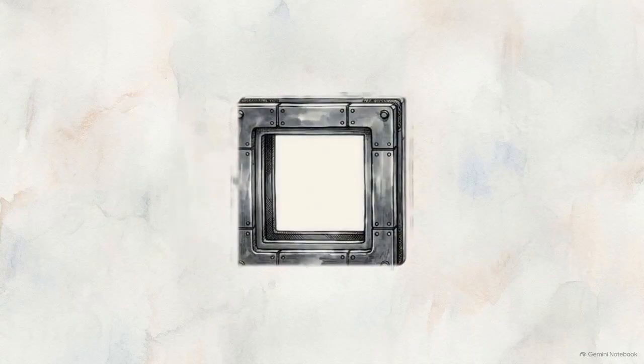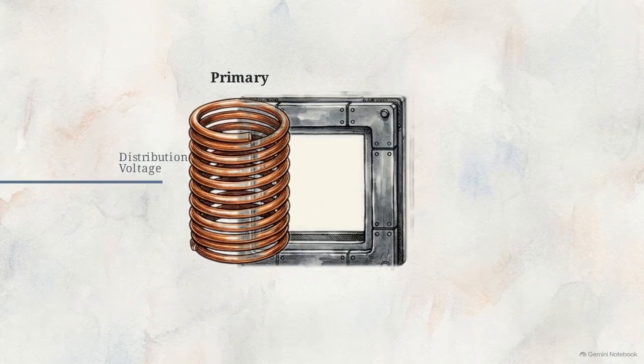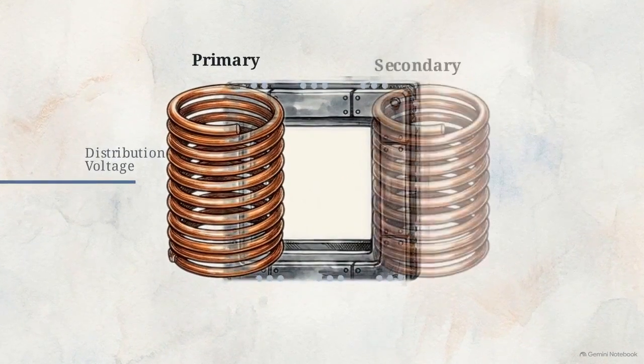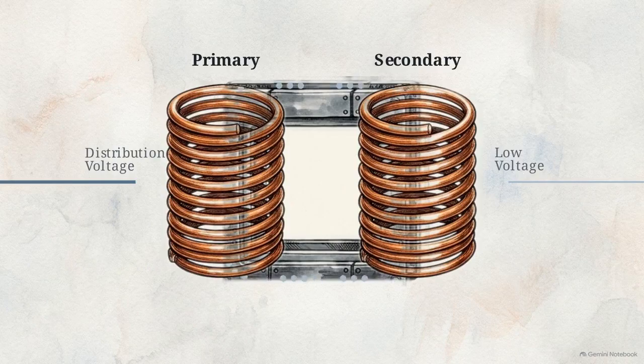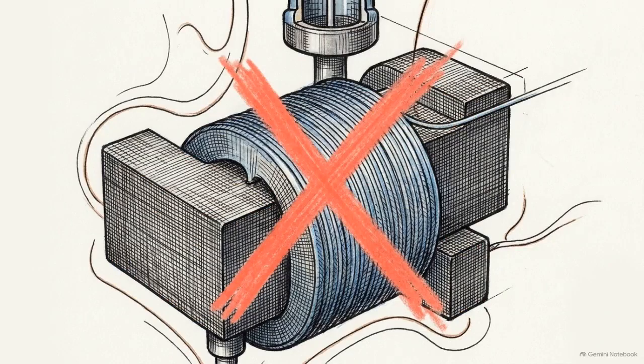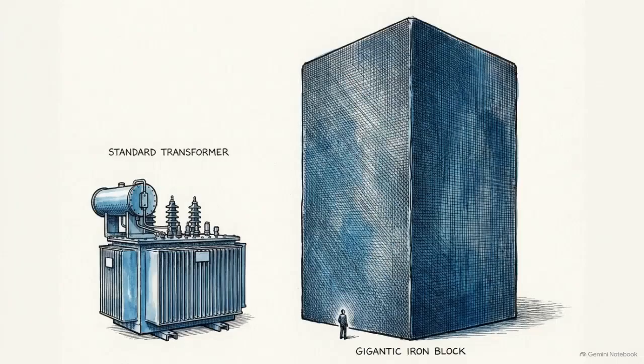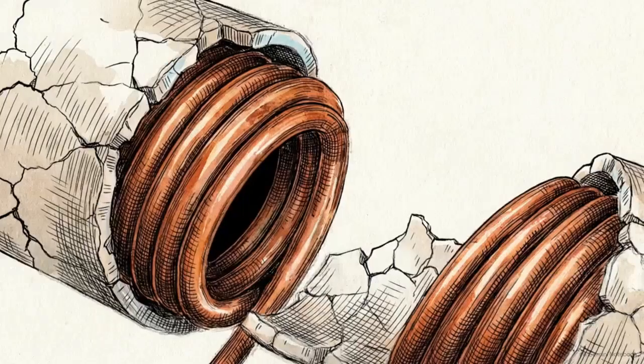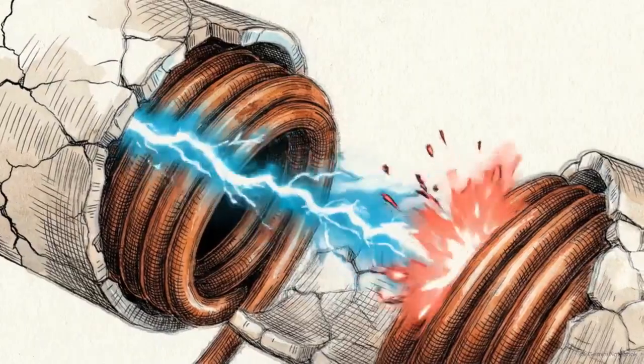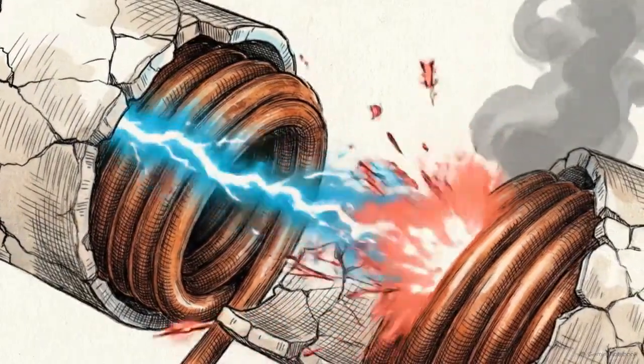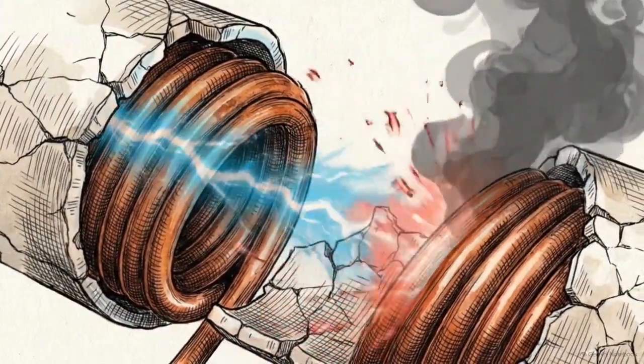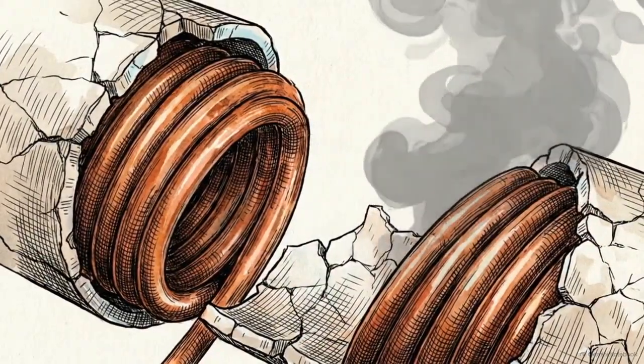At lower distribution voltages, engineers measure power using a standard inductive potential transformer, which steps down the voltage using magnetic coils wrapped around an iron core. But scaling that magnetic induction principle up to 765 kV physically breaks down. A standard iron core designed for that much potential would have to be massive. The volume of copper and the amount of insulation required to prevent a catastrophic arc flash make a pure magnetic step-down economically and structurally unviable.